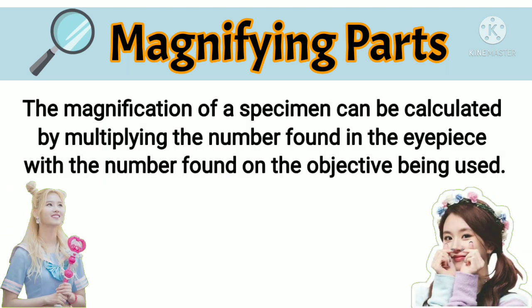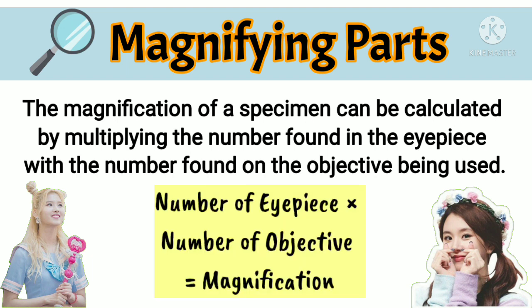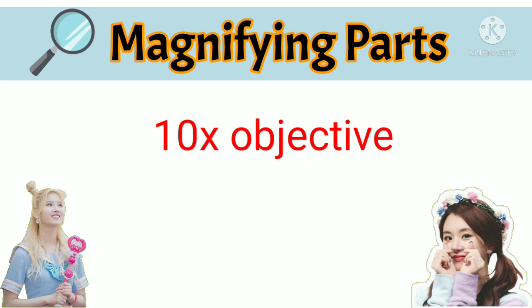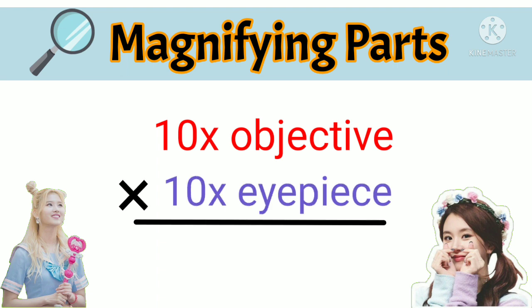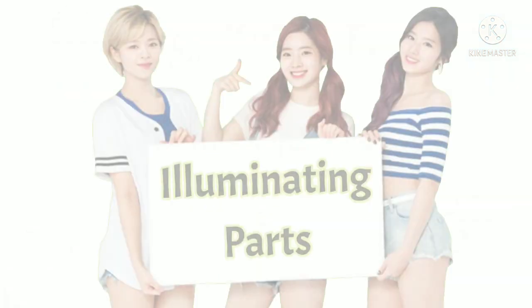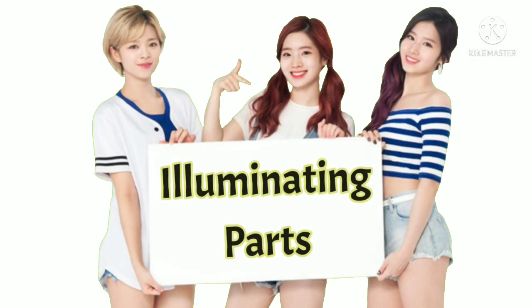Remember, the magnification of a specimen can be calculated by multiplying the number found on the eyepiece with the number found on the objective being used. So, if a specimen is viewed using a 10 times objective and a 10 times eyepiece, it will be magnified 100 times. Next are the illuminating parts.